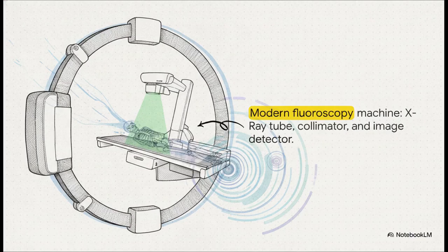So you might be wondering, how do we actually film this internal medical movie? Well, this right here is the highly specialized machinery that makes it all happen, a modern fluoroscopy machine. Up at the top, or sometimes tucked below the table, depending on the exact setup, is the X-ray tube. This tube operates at seriously high voltages to generate the X-rays by accelerating electrons. Right below that, we have the collimator, which physically shapes the beam. And then, capturing all the magic, is the image detector.